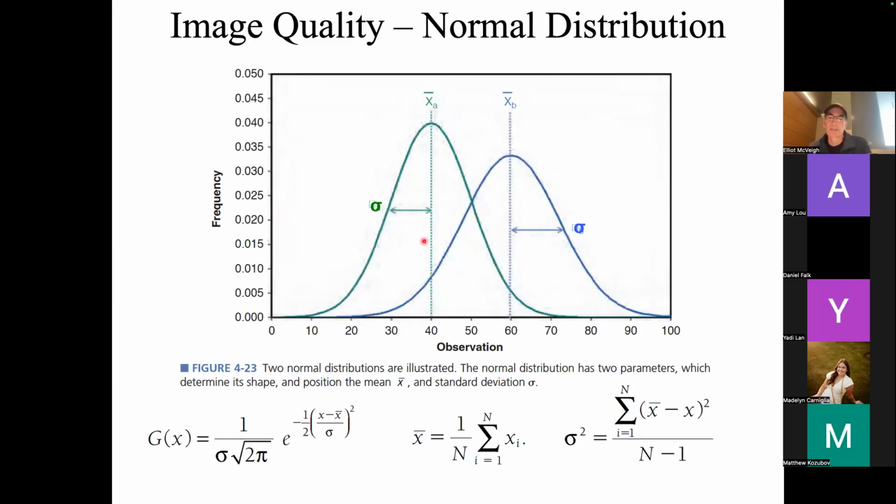So in looking at the signal to noise for these different reconstructions, different filters, we can go back to what we looked at before. Remember on the problem set, we were actually measuring signal to noise in CT. We have the mean of the background. We have the standard deviation of the pixel values in the background. We have the mean of our target, right, which is, say, a disk or something like that. And then the standard deviation inside the target. So if it's a disk, I can look at the standard deviation in the disk.